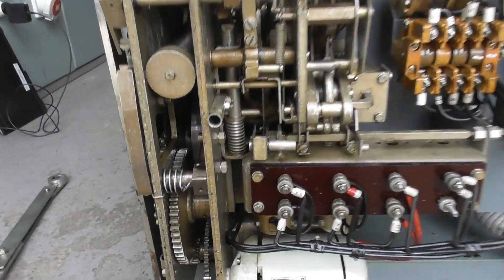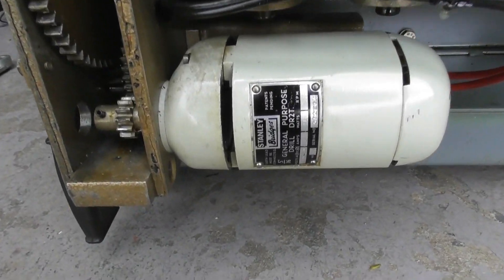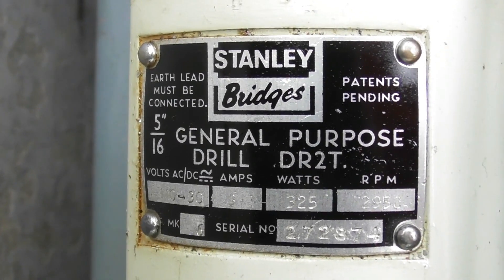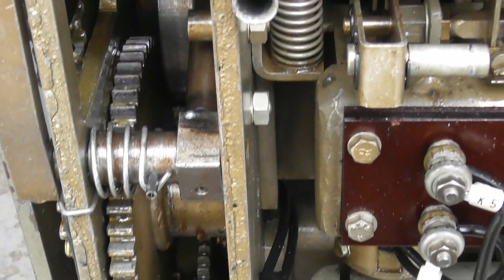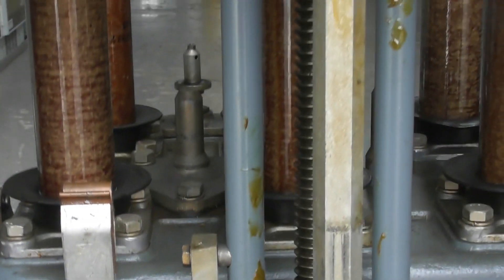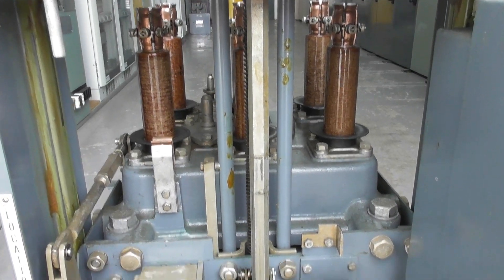Quite a bit of crap has leaked out of it. So you've got the winding motor here — DC motor, 110 volts. These motors run on DC. Reduction gearing here, charging springs, and that will operate the mechanism which opens or closes the contacts in the circuit breaker.